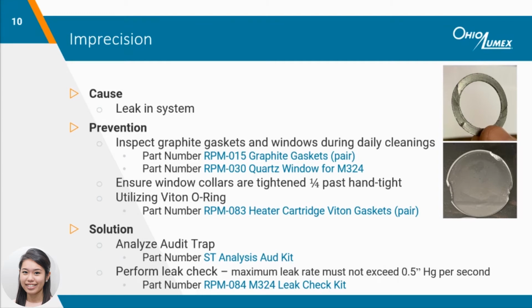A leak can also occur between the heater cartridge and the rest of the attachment. Utilizing a Viton O-ring will also help prevent leaking. This is updated from the old white insulation style gaskets, so make sure you have the right one. If you do suspect a leak during analysis, you can analyze an audit trap at any time to confirm.